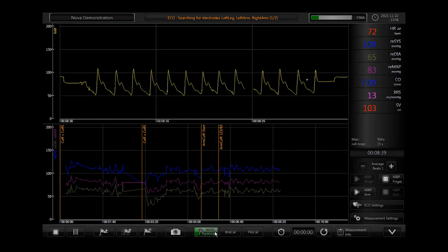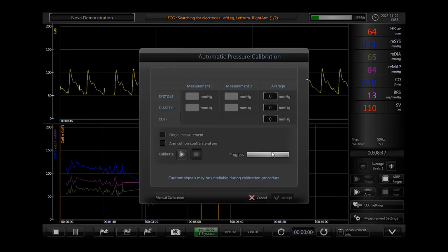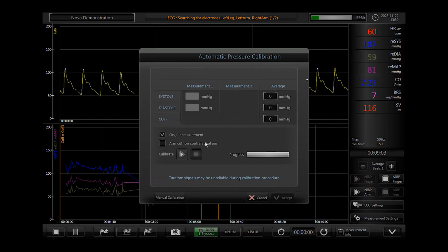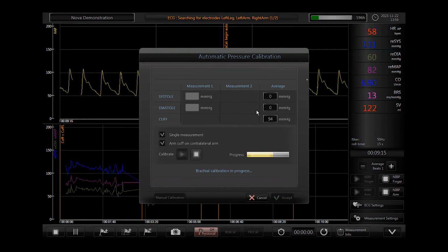To add an additional level of accuracy, the finger arterial pressure is compared to a brachial measurement using the brachial calibration button. Typically, you would take 2 measurements and then average them using a brachial cuff. For this demonstration, I'm just going to do a single measurement. You can also select the arm that you'll be using, as that can alter your data. Once the brachial calibration is complete, it will produce a delta. Based on that delta, you can decide whether you need to adjust your finger cuff or not. Typically, if the delta is less than 20, you can have confidence that your finger cuff is placed appropriately. If it's over 20, then you might consider adjusting the fit of the finger cuff.